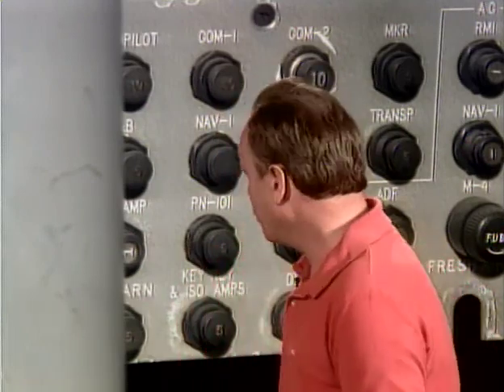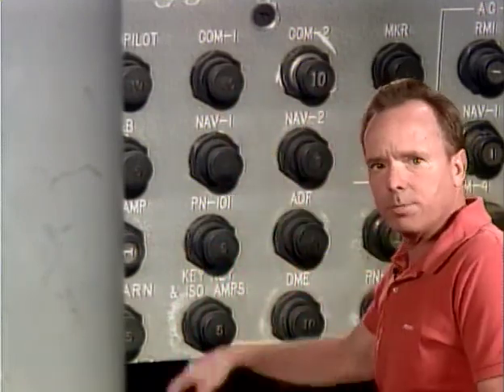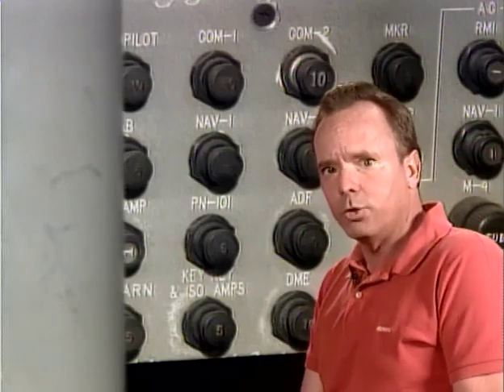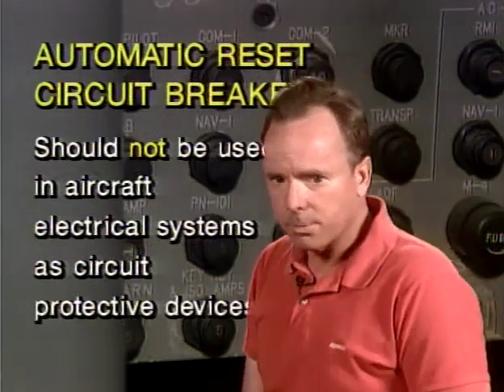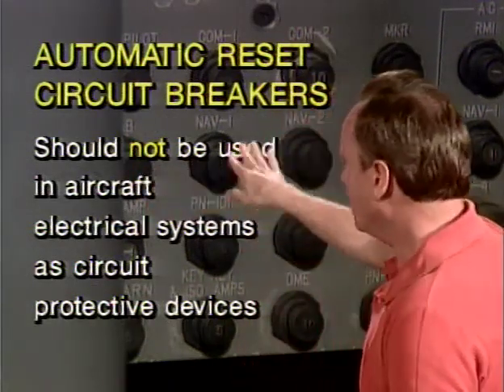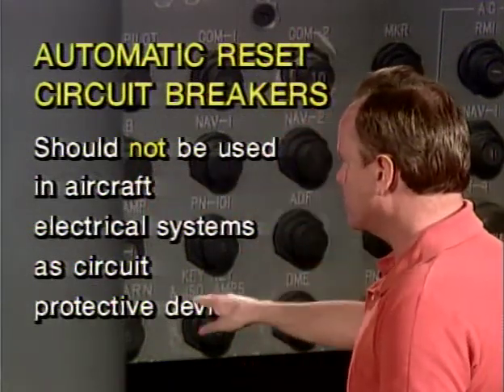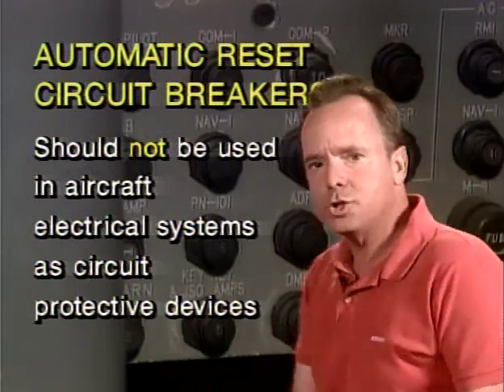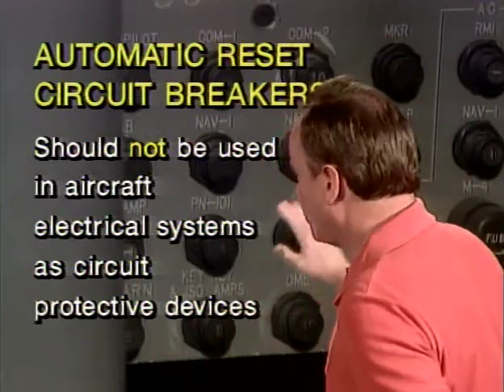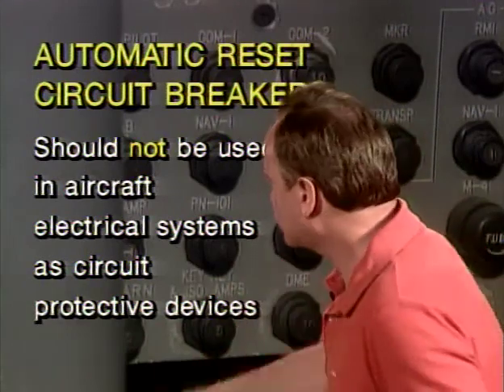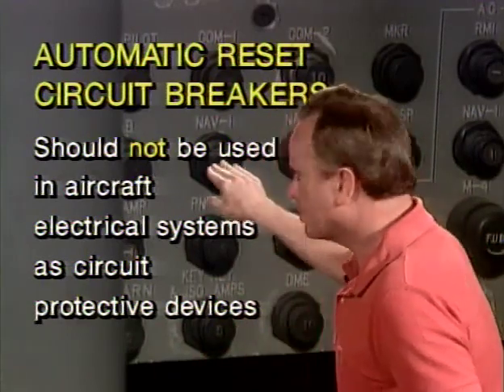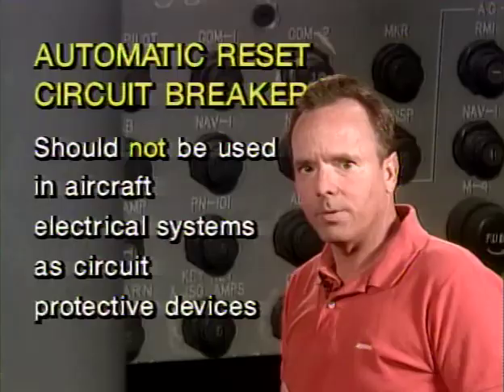Now, the circuit breaker in the instrument lighting system, for instance, protects the wiring from too much current. That's the whole idea of a circuit breaker, to protect the wiring from too much current. Now, an automatic reset circuit breaker should not be used in aircraft electrical systems as a circuit protective device because you want the pilot to be required to take some kind of action to reset the circuit breaker. You don't want it automatically being reset.